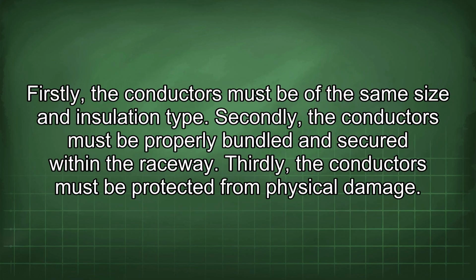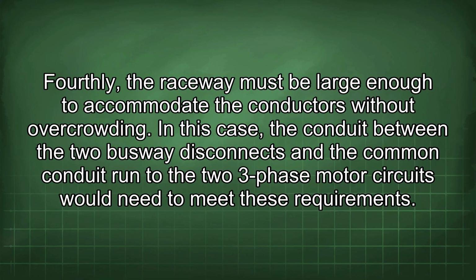Firstly, the conductors must be of the same size and insulation type. Secondly, the conductors must be properly bundled and secured within the raceway. Thirdly, the conductors must be protected from physical damage. Fourthly, the raceway must be large enough to accommodate the conductors without overcrowding. In this case, the conduit between the two busway disconnects and the common conduit run to the two three-phase motor circuits would need to meet these requirements.